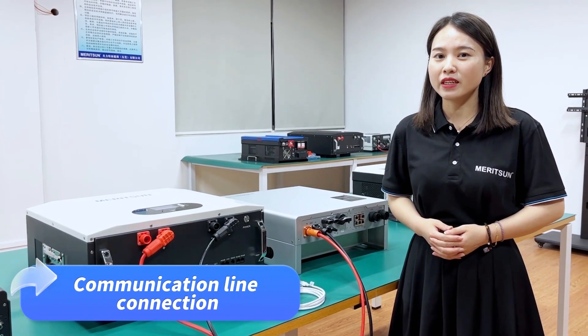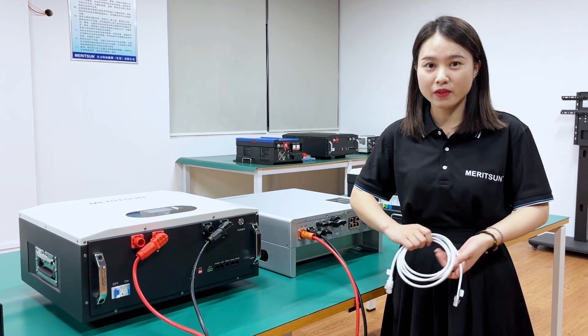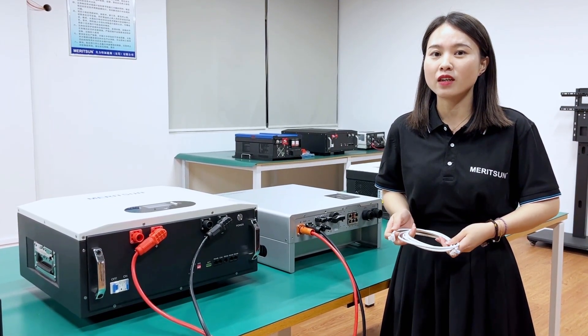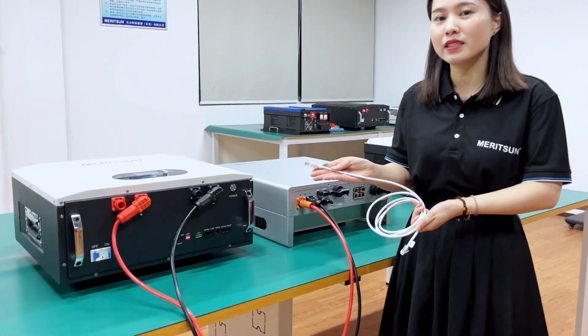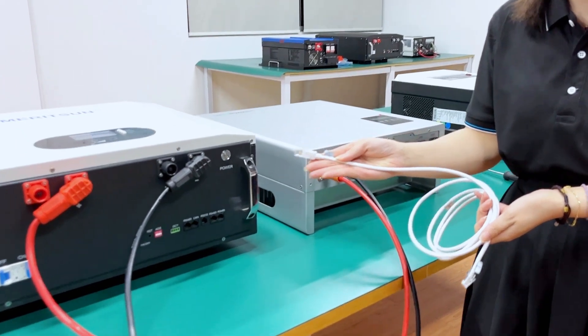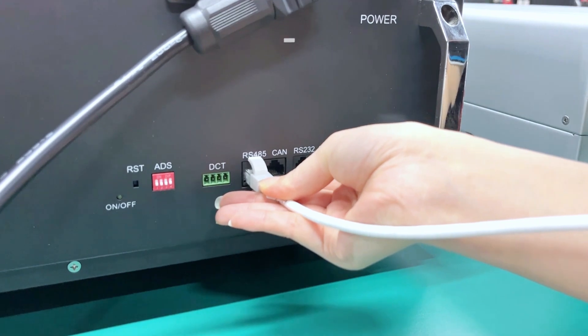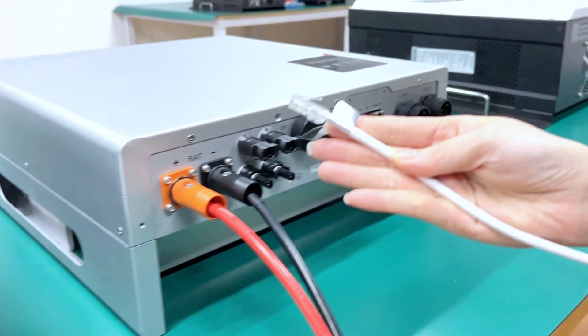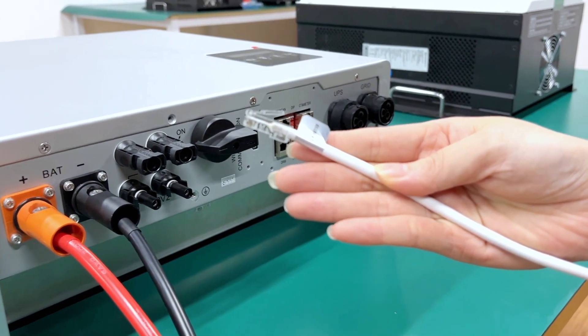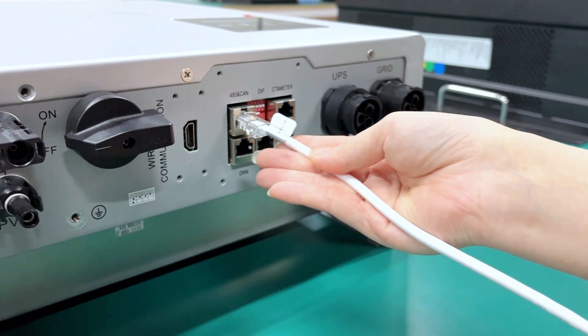Now let's set up the communication for the battery and inverter. We need to use this communication cable with the Meritsun inverter. The cable end marked 'battery' is connected to the RS485 port of the battery, and the other end marked 'inverter' is connected to the BMS communication port — RS485 and CAN — of the inverter.